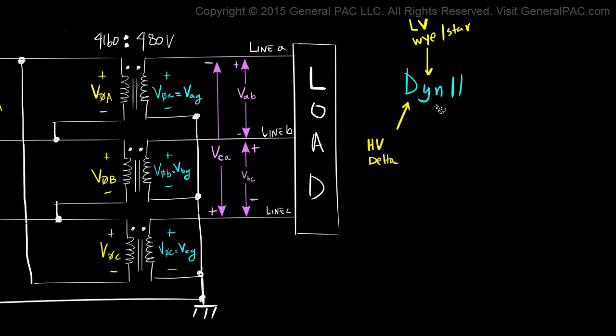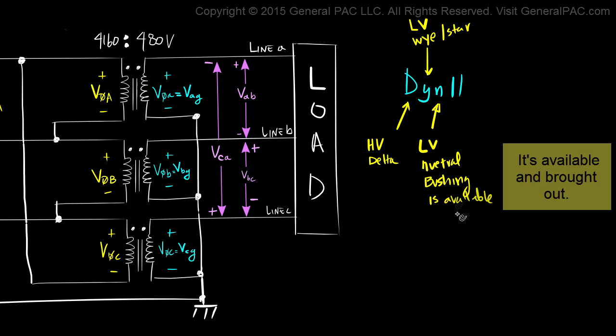Because the N comes directly after the Y, the N tells us that the low voltage windings neutral bushing is available. Now, the low voltage neutral bushing is available but that doesn't mean that the neutral bushing is actually grounded.